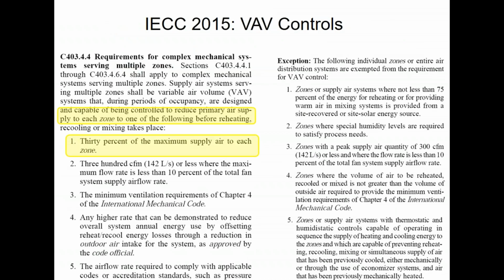This comes up as well in the code. It's not new in the code, but it's not dealt with properly sometimes. Generally speaking, you're not allowed to reheat air that you've already previously cooled. However, VAV systems have an exception. If they throttle the VAV damper back down to 30% of the supply CFM, you are then allowed to have a reheat coil, meaning hydronic coil or electric reheat or one of those types of things. So you are allowed to do it if you have VAV. You cannot do constant volume reheat. That is not allowed. But VAV reheat is allowed if you follow the rules listed here.